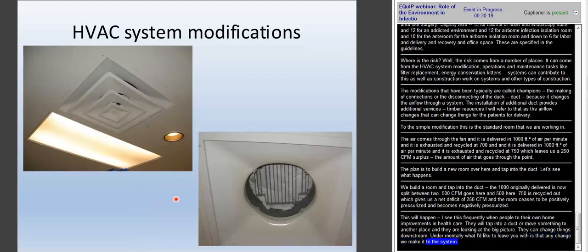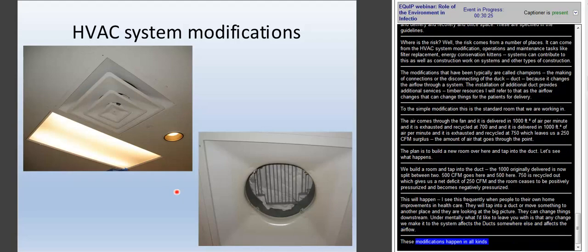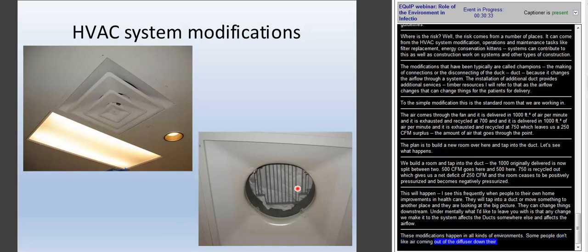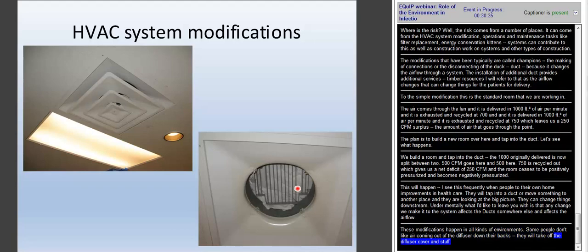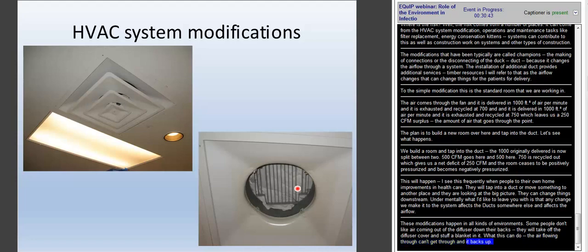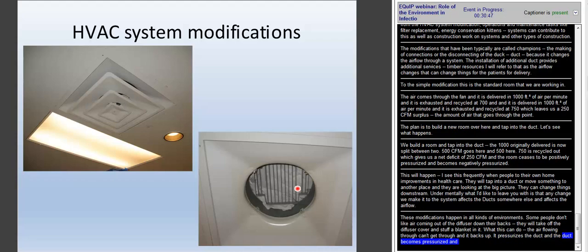And these modifications happen in all kinds of environments. Some people don't like air coming out of a diffuser and blowing down their back, so they will take off this diffuser cover and stuff in a blanket. And so what that blanket can do is that air that was flowing through there can't get through, so it backs up. It pressurizes the duct. That duct becomes pressurized, and through leakage points in the duct will pressurize the above ceiling space, which is where dust accumulates in the environment, and will push that dust down into the environment.